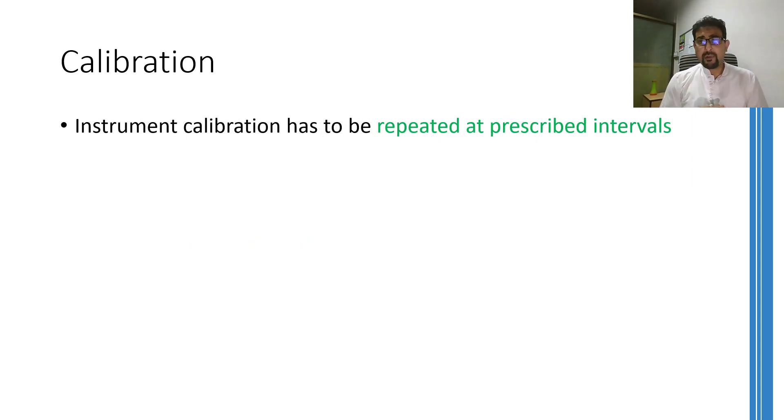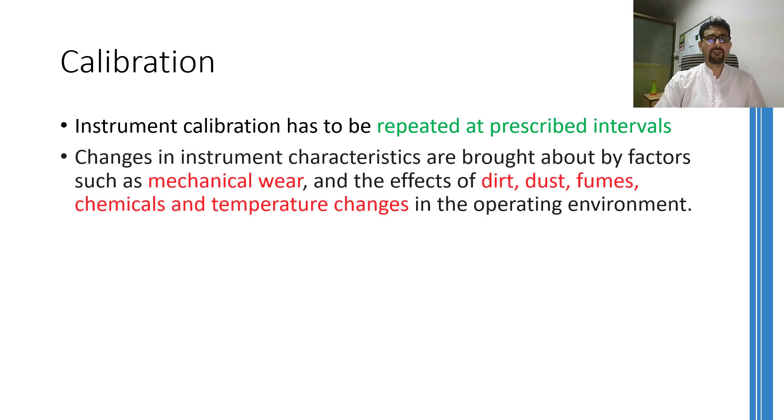Depending on the type of industry or the type of application where some instrument is being used, the calibration should be repeated at prescribed intervals because no matter how safely you are using any instrument, there are chances that its characteristics will change due to its mechanical wear, dust, fumes, changes in temperature and pressure. However, the frequency of this calibration depends on the application and should be analyzed very carefully because when you are going to check the calibration of any instrument, this means that you have to remove that instrument from the process or in some serious cases, you might have to stop the whole process. Therefore, it is not something that you can easily do on daily basis or even weekly basis.